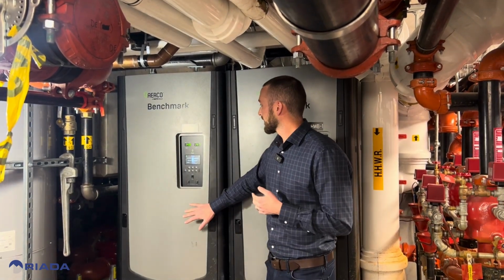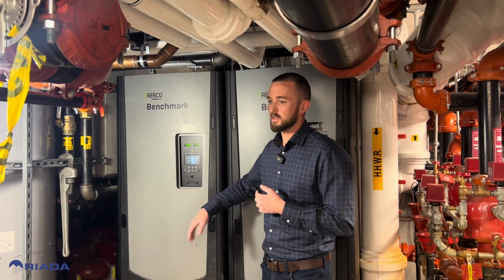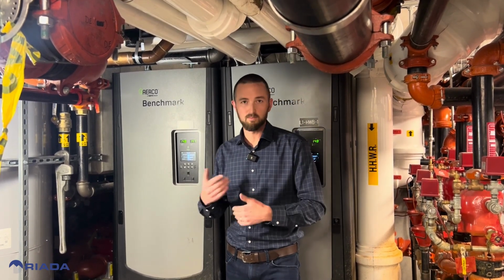Another thing with the Benchmark series is the 439 stainless steel heat exchanger. Because of the material construction, it has a lower coefficient of expansion. So less expansion and contraction during operation, less wear and tear. That allows us to offer industry-leading warranties of up to 15 years on the Benchmark series. So that means a lower embodied carbon for less equipment replacements over the life of the building.